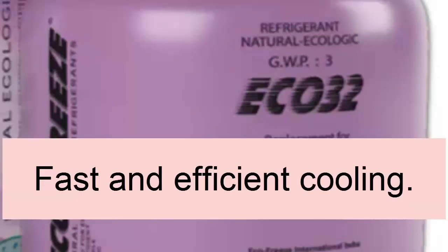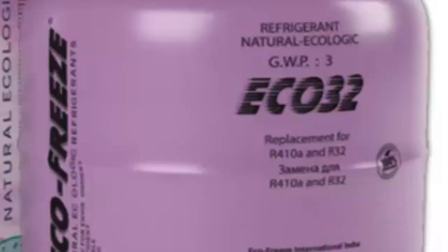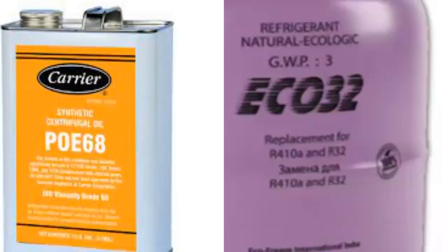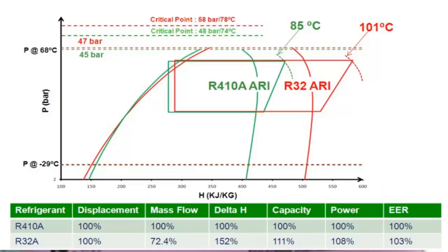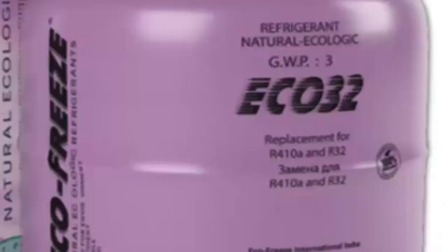2. Rapid cooling effect. 3. Acceptable energy efficiency. 4. ECO32 is compatible with all common lubricants — mineral and synthetic oils, PAG and POE. 5. ECO32 operates at lower pressures than synthetic refrigerants.